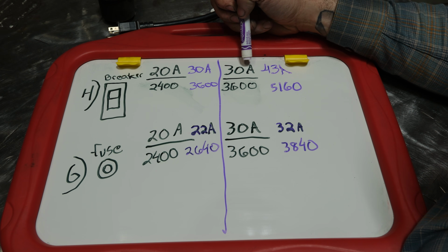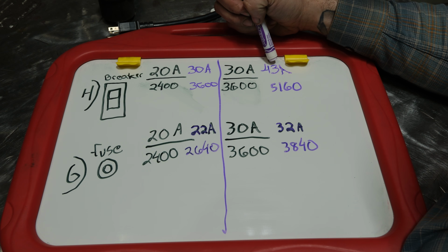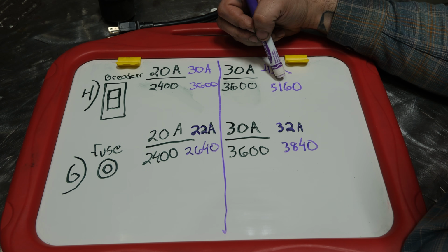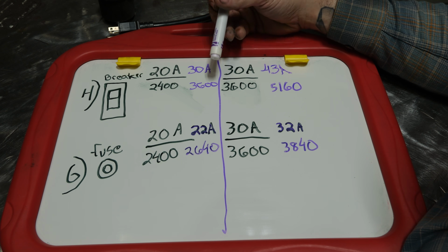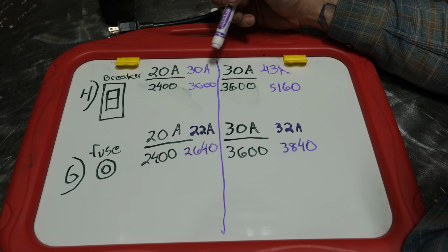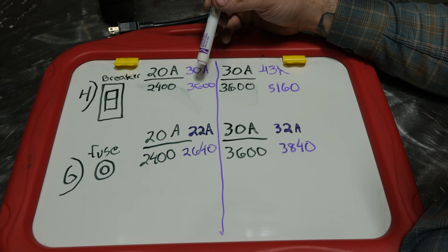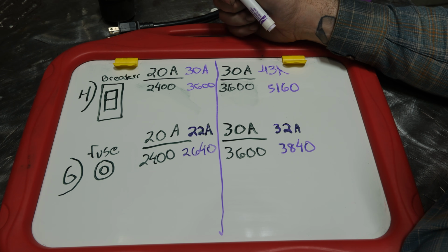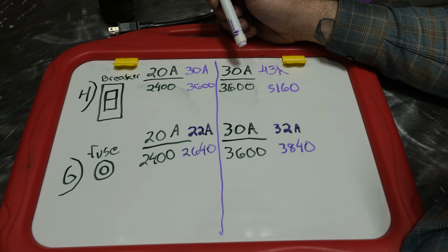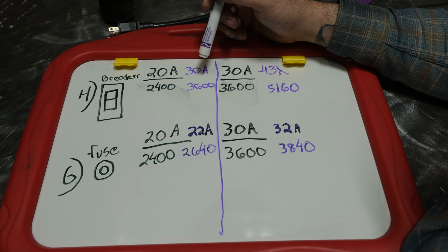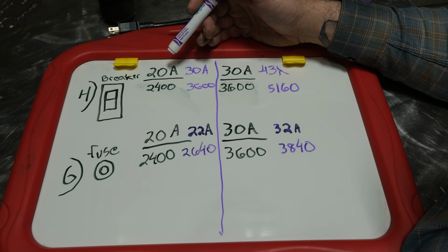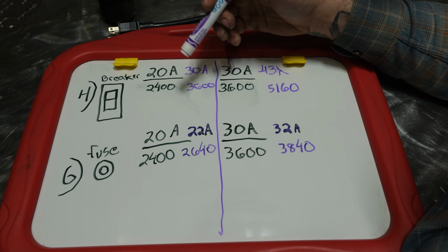On a 30 amp household breaker, you can oftentimes pull 43 to 47 amps through it, which is at least 5,160 watts versus the face value of 3,600. Household breakers and the household electrical system have so much overhead available that overloading the breaker isn't much of a concern. The problem with a generator is you simply don't have that.